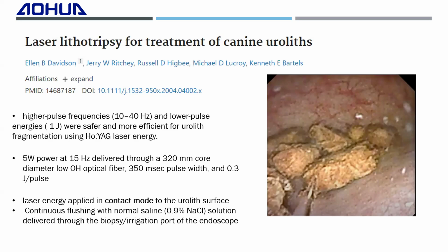To be honest, our YAG lasers are up to 20 watts. So you see that we use only 5 watts power at 15 hertz delivered through a 320 fiber. So I give you all these details because if you need to buy the instrumentation, you need to know which kind of fibers, which kind of lasers and everything, and to which watts, hertz, and adjustment you need to put your laser machines. So most of the time in urology, we use a 200 fiber, or a 320 or 365 for the uroliths. And it's more than adequate.